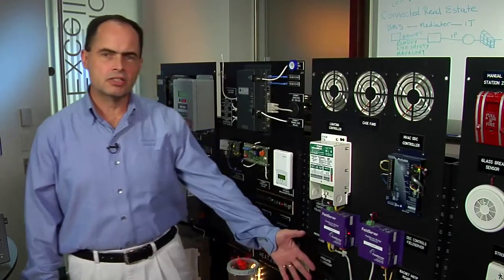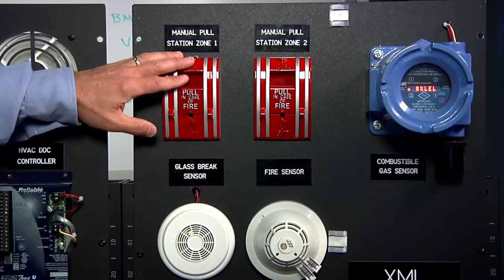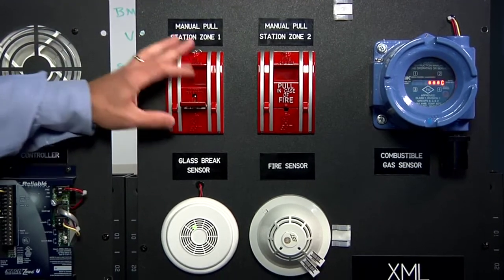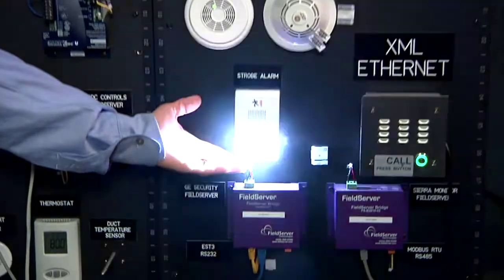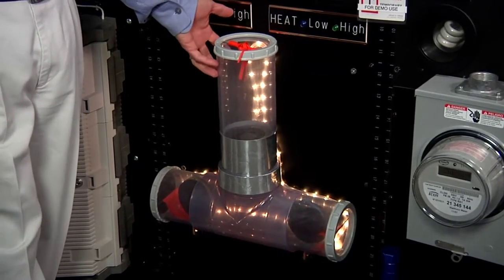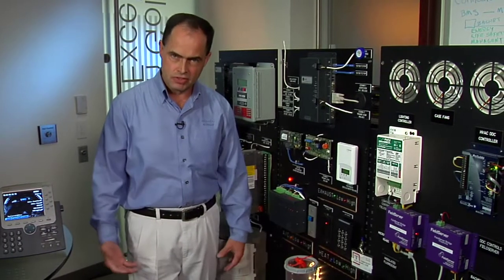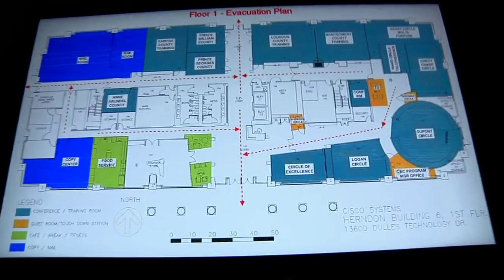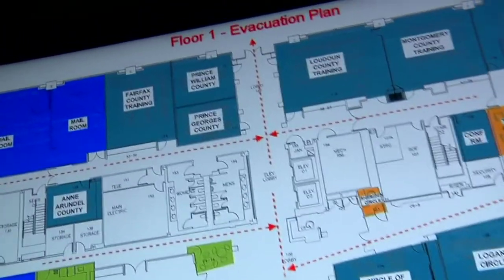Now let's look at how we can extend a traditional fire and life safety system beyond what we normally expect. Here I have a fire pull station — I'll go ahead and pull zone one. We see strobing and alerting as expected, but notice the HVAC system also cut off completely automatically. We're notifying safety, security, and the facilities manager via two-way radio that a fire incident has been indicated, and we're putting up a custom evacuation map on the digital sign using a digital media player connected to the IP network.